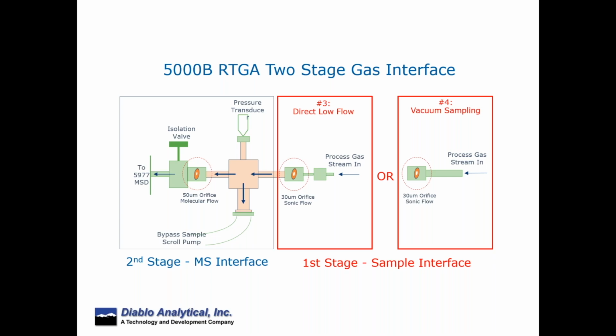And then the fourth option is, because of the design here and because mass spectrometry is a vacuum technique, we can do vacuum sampling. Now, the vacuum sampling may be down to 20 torr, so we're not talking about extreme levels of vacuum. But those are the four different interface options, and they're very easy to change and configure between the orifices if you want to change them or if they get plugged. It's just a VCR fitting that you simply spin open, put a new one in, and retighten.